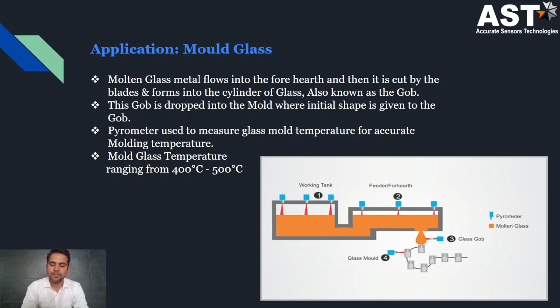This is the portable glass mold pyrometer, specially designed to measure the temperature of glass mold applications. This is a portable, robust, lightweight, and battery-powered non-contact type pyrometer. The temperature range is from 250 degrees Celsius to 600 degrees Celsius. This PGM consists of an adjustable fiber optic probe with detector and the electronic part. The fiber optic probe can sustain temperature up to 250 degrees Celsius, and the temperature measurement can be carried out by touching momentarily the tip of the probe to the target surface.